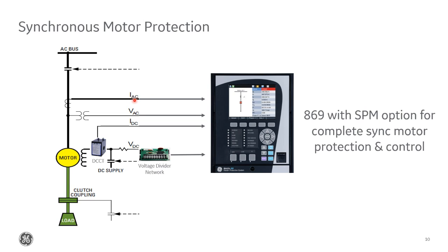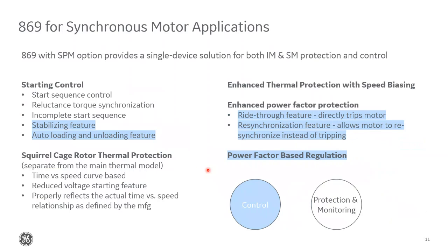You still have your usual line current and voltage signals coming to the relay. You'd still use a DC CT to provide the field current signal minus the calibration module. We do that processing directly in the 869. And down here, basically the same thing. We have an external voltage divider card that steps down the DC voltages, and then they're brought to the 869. So we'll talk a little bit more about this hardware in a moment. First, let's go over some of the key protection and control elements that the 869 with the SPM option offers.